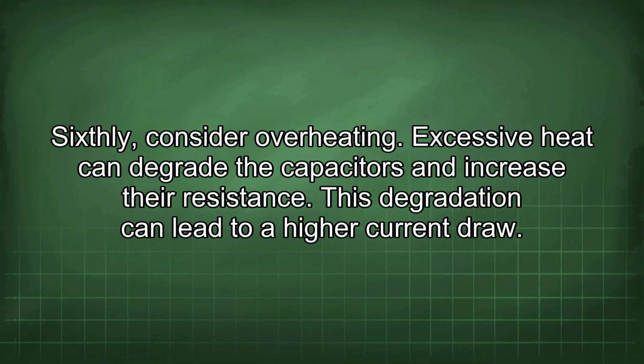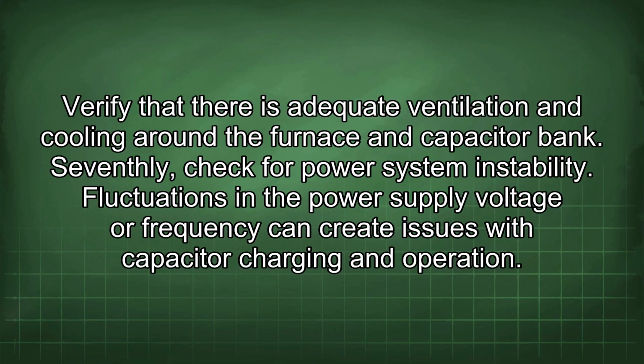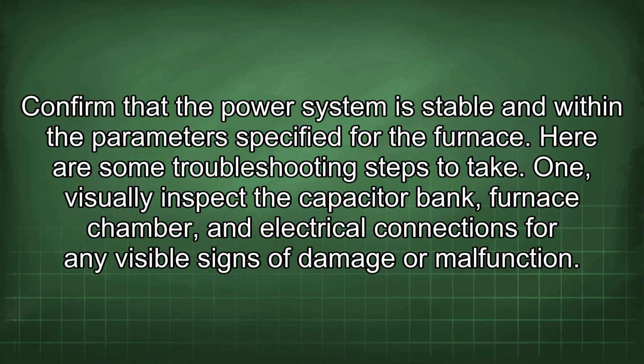Sixthly, consider overheating. Excessive heat can degrade the capacitors and increase their resistance. This degradation can lead to a higher current draw. Verify that there is adequate ventilation and cooling around the furnace and capacitor bank. Seventhly, check for power system instability. Fluctuations in the power supply voltage or frequency can create issues with capacitor charging and operation. Confirm that the power system is stable and within the parameters specified for the furnace.